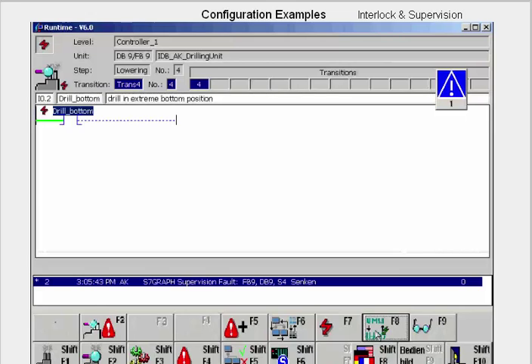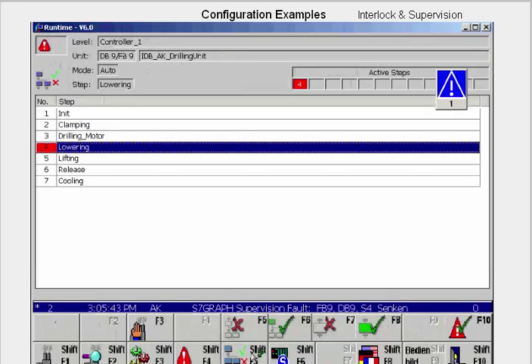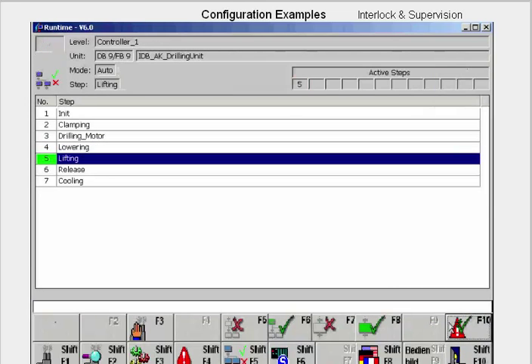Another click on F8 shows us the address in the ladder view. With Shift F5, we switch to the sequencer view in which the number of the blocked step is marked red. After clearing the fault, we have to acknowledge the supervision fault — only then is processing of the sequencer continued.